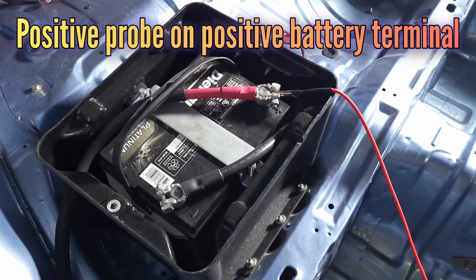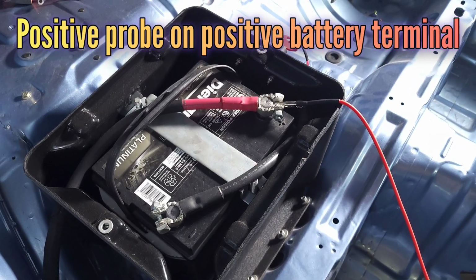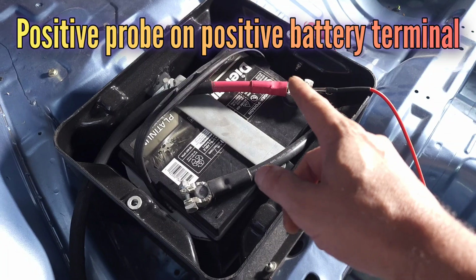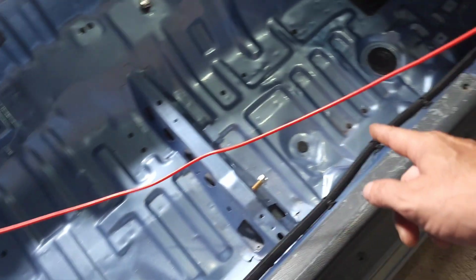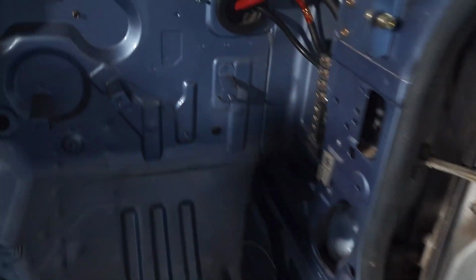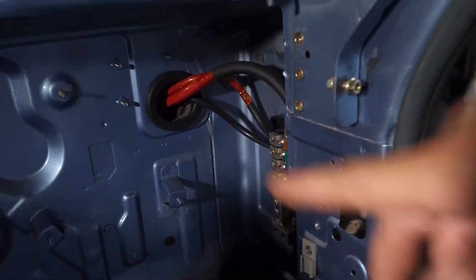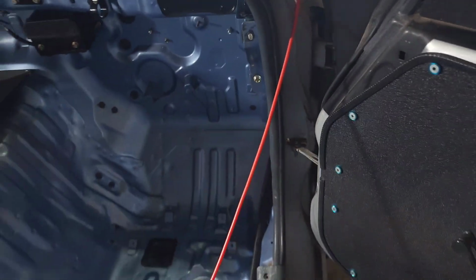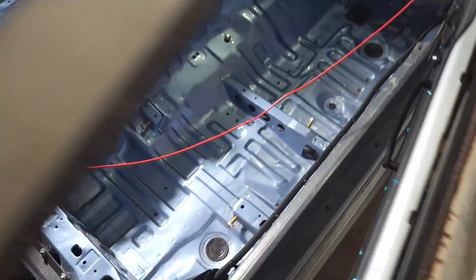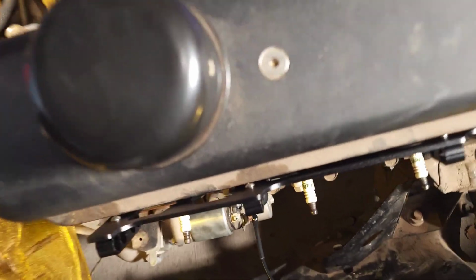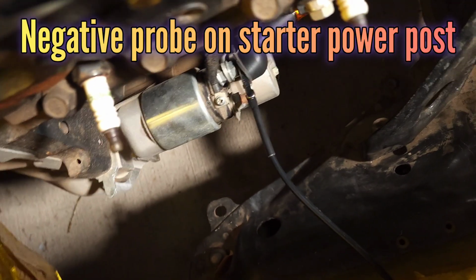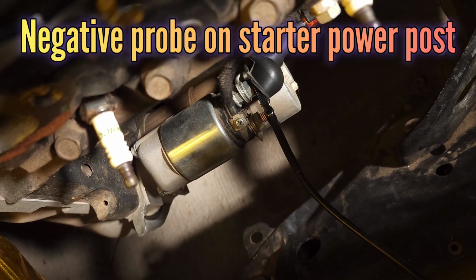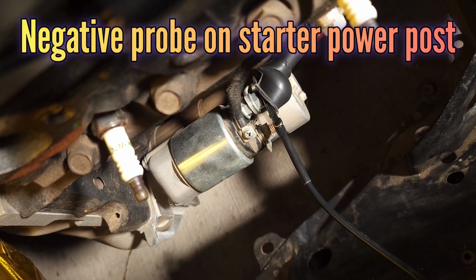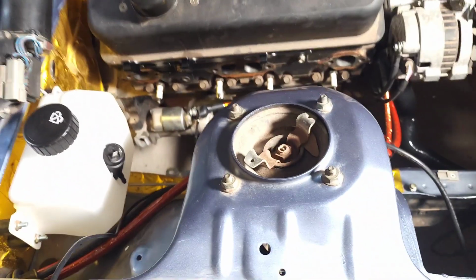Okay, let's get into the setup. So what we're going to be testing is the main battery cable all the way to the starter post. So essentially we are verifying the voltage drop on this cable. That's the only component besides a small interruption there at the distribution panel. So all of this is added together, and we are measuring the entirety of the cable all the way to the main power post on the starter. So everything in between, every connector, every ring terminal, all that stuff.